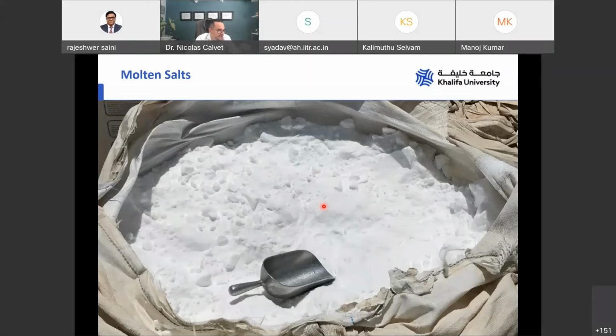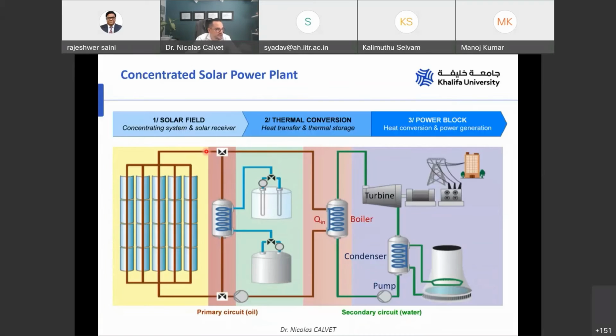So you have on the left the solar field, a conventional parabolic trough plant using synthetic oil. The synthetic oil goes to the heat exchanger to produce the steam for the turbine. And during the day, when you have too much energy, one part of the oil will be sent to another heat exchanger where it will exchange heat with the molten salt. So you have a two-tank system. One tank is called the cold tank, but when we say cold, it's relatively cold, because the temperature is 290 C.